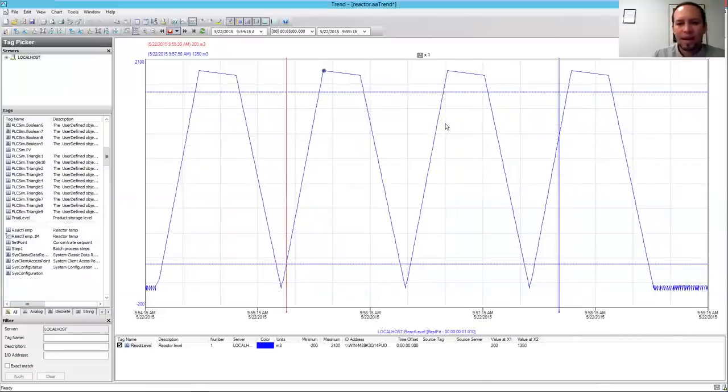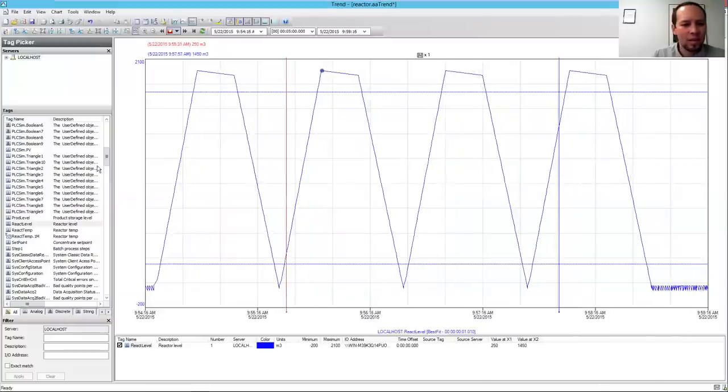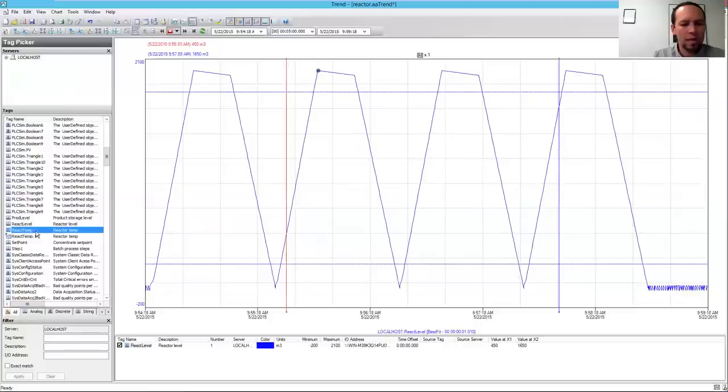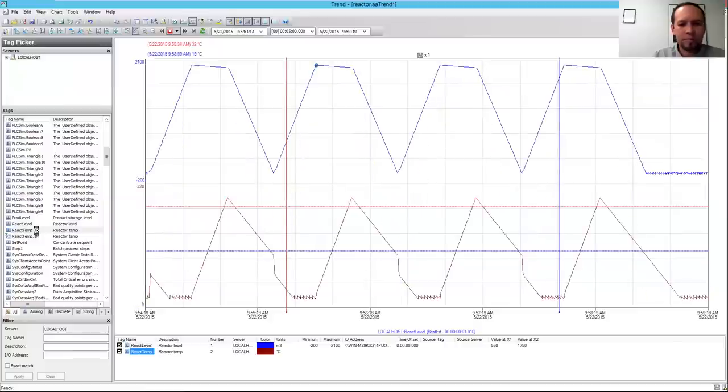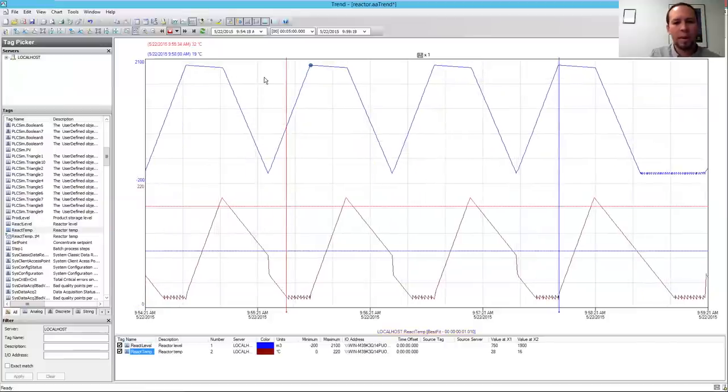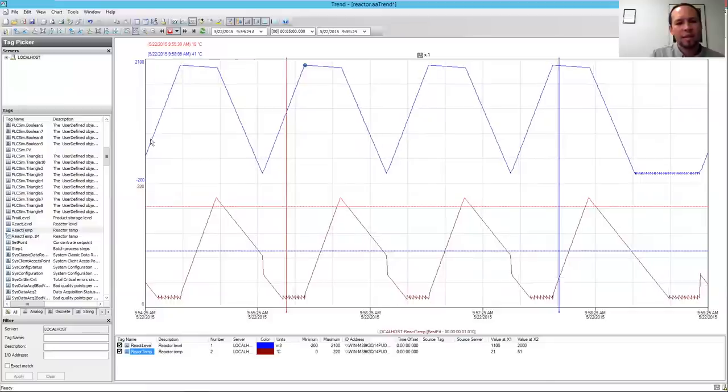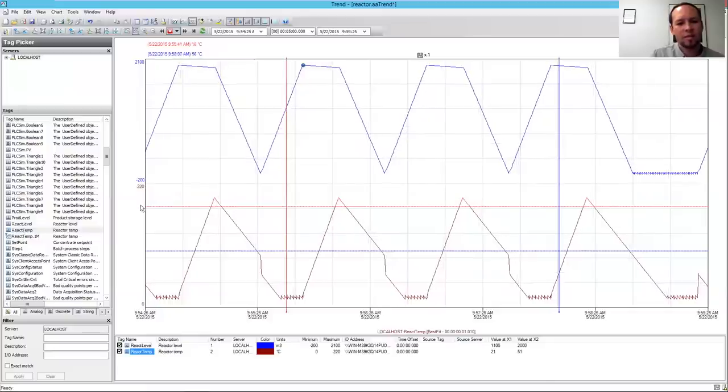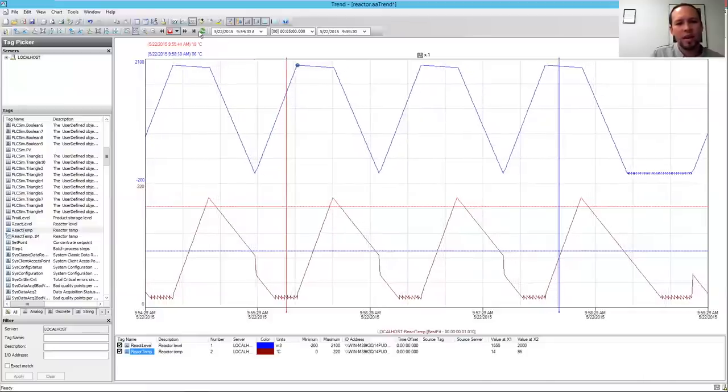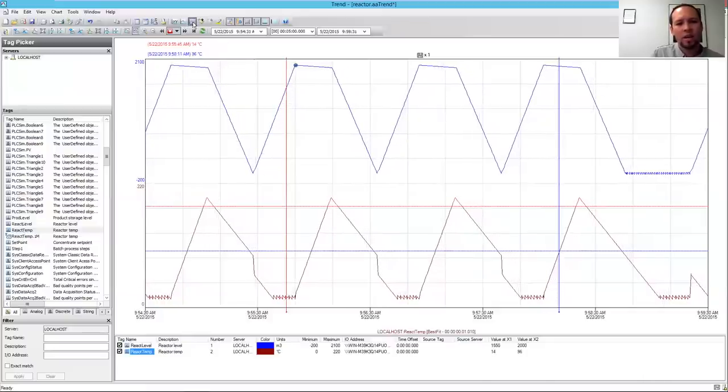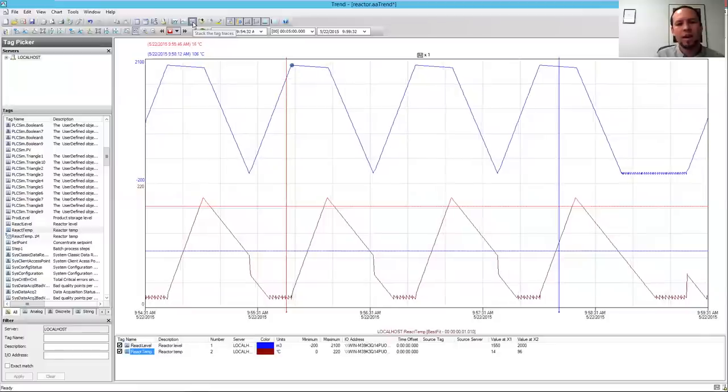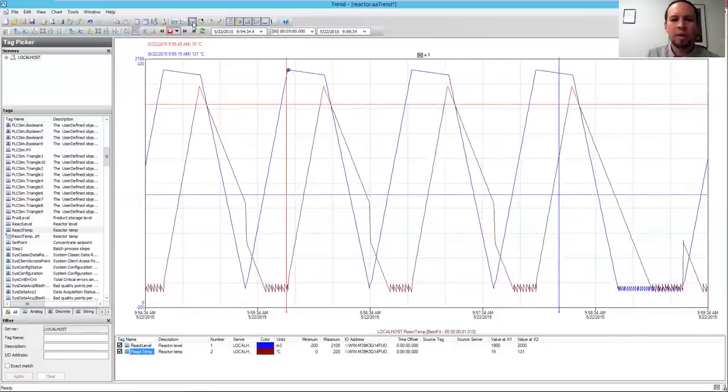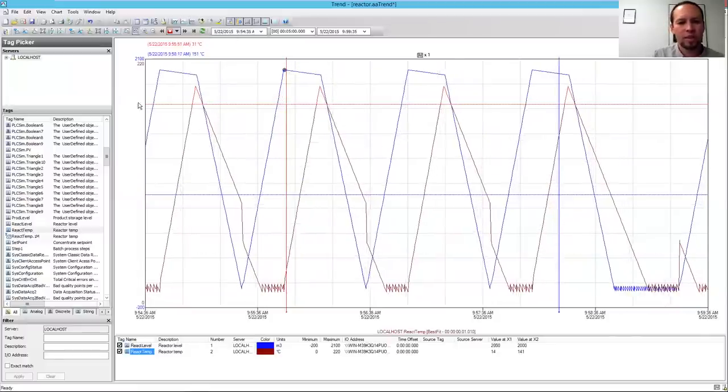I can add a second tag here, and I'll just double-click on React Temp over here, and now I've got both React Level and React Temp, and I can see right now the data is stacked. The two tags are stacked. They've got different value axes here on the left-hand side, or I can click the Stack the Tag Traces button, and that will put them in overlaid, so now they're actually sharing the same value axis.